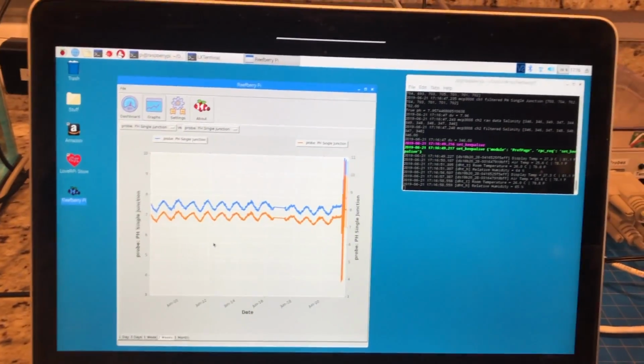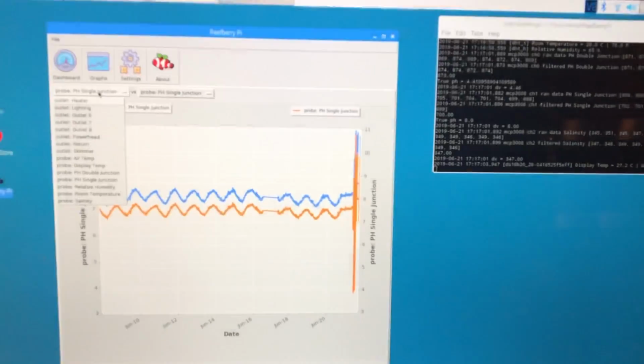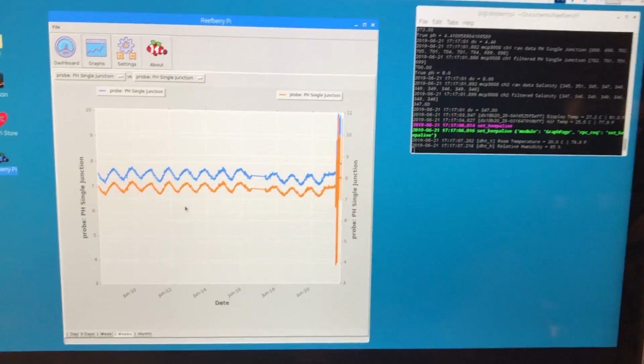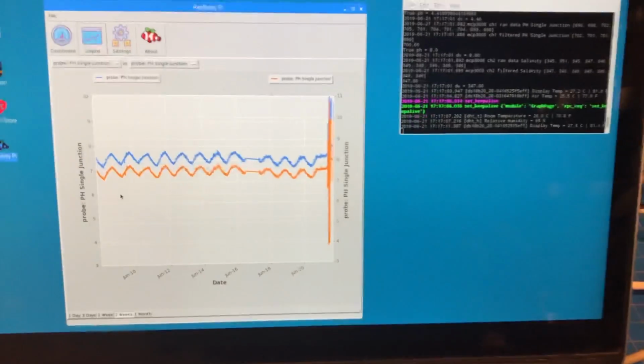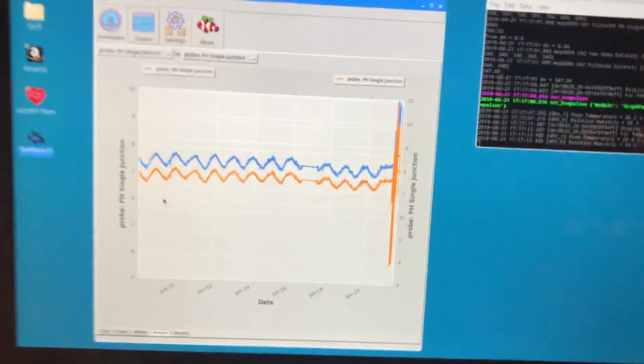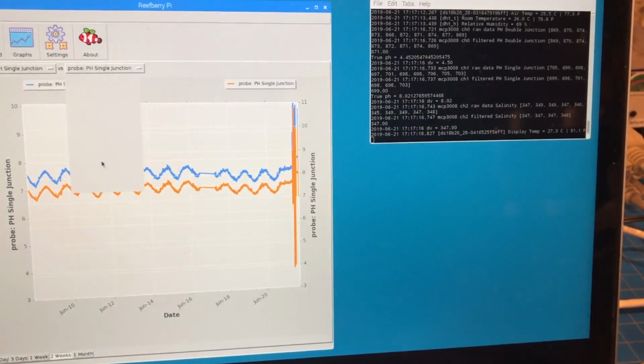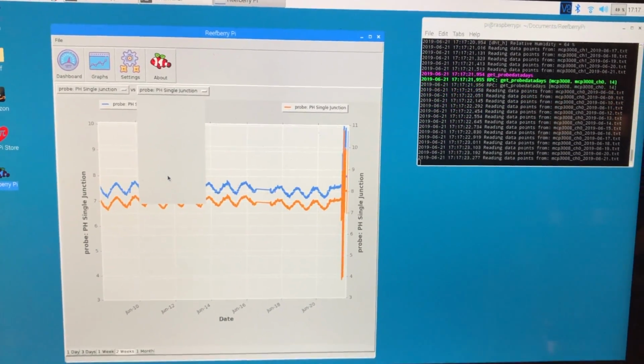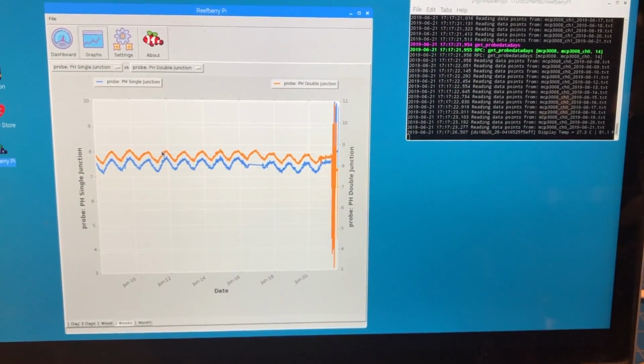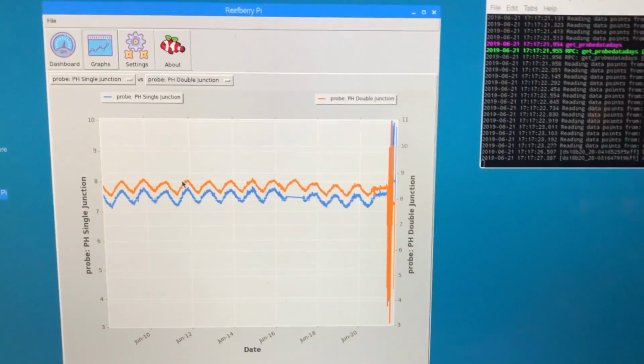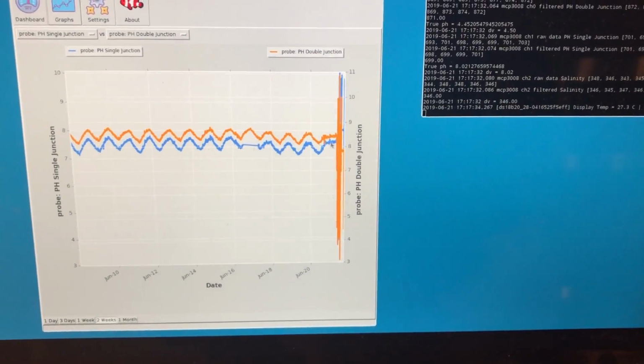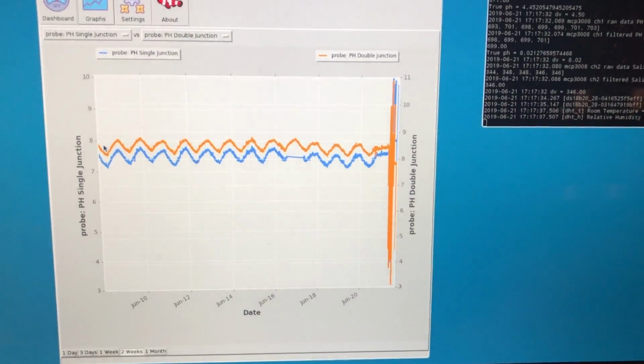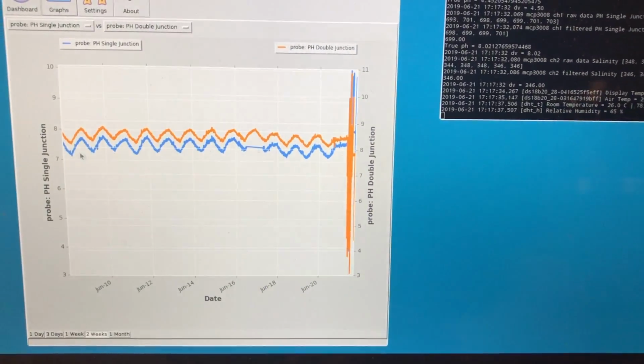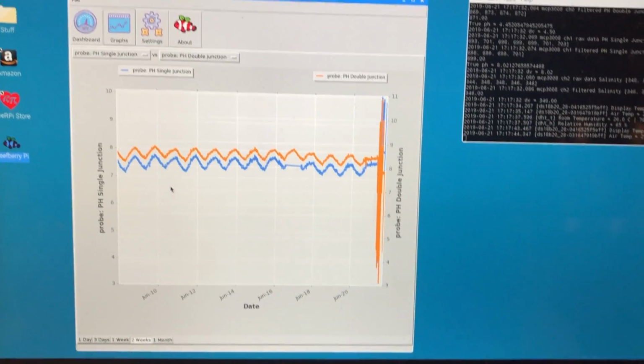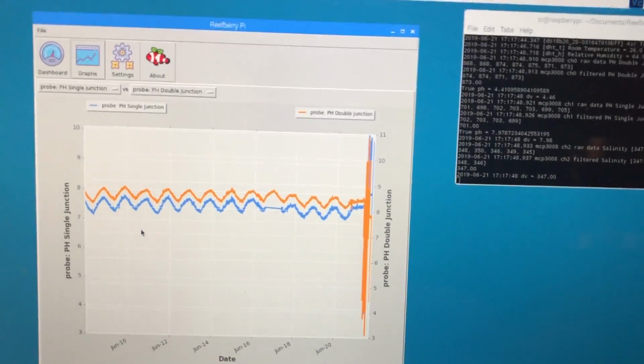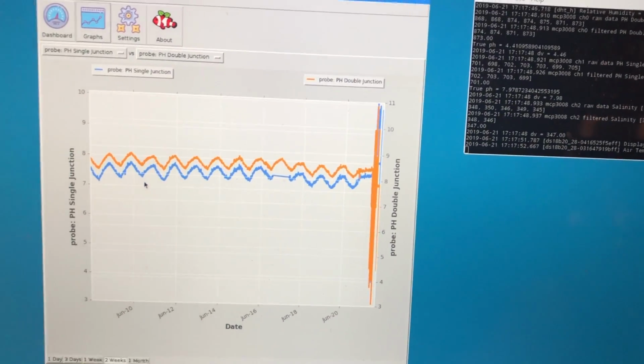And then the graphing feature, which I have here, where you can overlay certain graphs for any of the outlets or probes where you're recording data. Here's the 2-week plot of my pH probes. Let's go pH probe versus, see if I can go to this one. Okay, so these were the two probes that I had, the single junction versus the double junction, while it was still alive. Over the 2-week period, even though these weren't calibrated properly and the numbers aren't exactly right, you can see that it was following the pH cycle that you would expect in your reef tank, where during the day it goes up and up and up, lights go off, it drops down, and it's up and down.